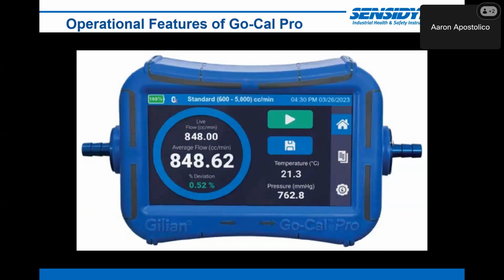So this is really a screenshot of the new GoCal Pro calibrator, and I'm going to call attention to a few features. So it does have directional flow. You can see the 2 arrows at the bottom of the molding pointing to the direction of flow towards the pump.